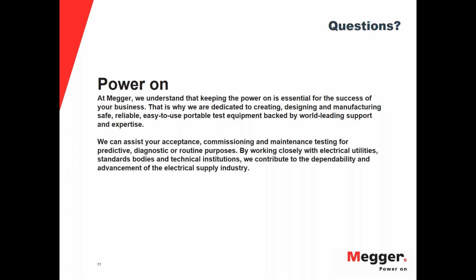Hi, Sanket here. The test interval refers to the time between tests, and when we say 25%, we mean 25% of service life. Service life is the life for which the battery is expected to be in operation, and that's provided by the manufacturer. It varies from model to model, but it's typically in the range of 10 to 20 years. So you can look at the manufacturer's specs and find out about the service life, and based on that, you can decide how often you want to run the test until you see the capacity degrading. All right, next question.